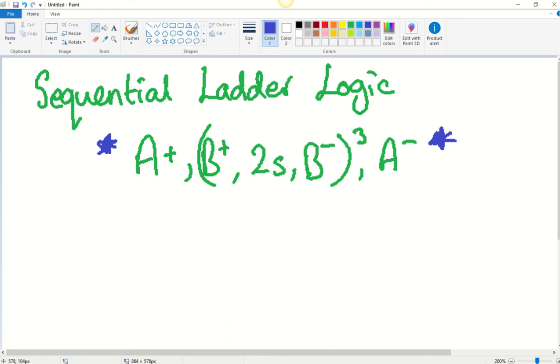You might get confused early looking at this — you're doing A plus, then B plus, then B minus, then jumping back and so forth. What we can do is use what we call a step relay approach, where we use memory bits or flag bits to signify that steps have happened. We then use those steps to trigger the output, so it's the markers acting as a middleman before we go to the outputs.